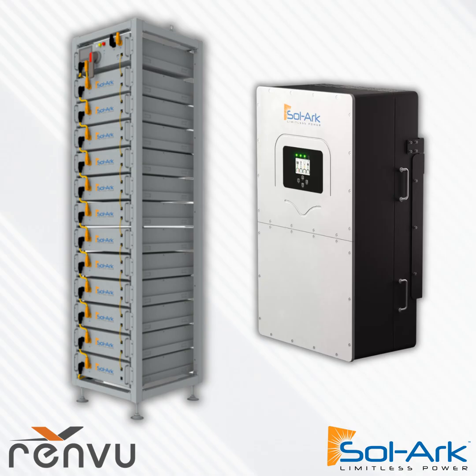With commercial, instead of doing whole building backup with a system not really sized large enough for that despite grid pass-through, the other option is to walk into the control room, look at the main switch, and ask the facilities manager which breakers are most important to back up. Maybe this one's for the refrigerators, or this one governs the lighting and security system. Then we put those sub panels onto the backup power system as the interconnection point, rather than powering down the whole building and doing a complicated supply side, line side tap.